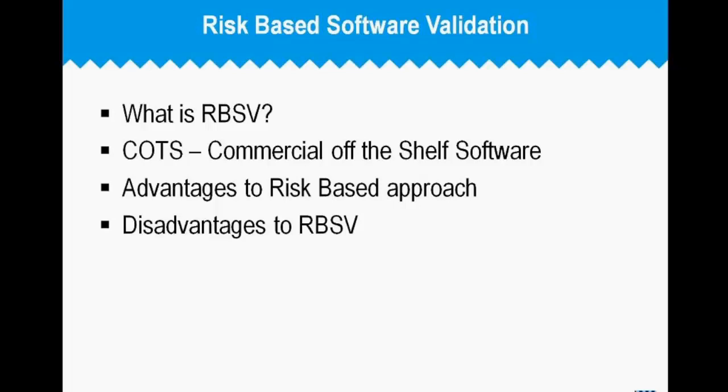Yeah, and actually, you make a really good point right there in terms of emphasizing COTS is also all the things inside your development environment and your support environment. If they're somehow influencing that medical device, then they're in scope for being under control.